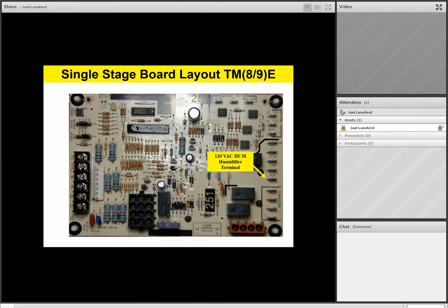One of the things I really like about the Champion furnaces is we do a lot of things on the board. You'll notice you don't have to have a lot of extra relays or controls or those types of things because a lot of that's built in on the board. So basically we have a transformer output, we have a humidifier output, we have an electronic air cleaner output, and that's all built in on the board. So we don't have to have special accessories or special controls for those components. We can actually power them up right off the board, and that's really nice because a lot of manufacturers, a lot of our competitors, require you to have a lot of accessory items, but we like to build a lot of that on the board whenever possible.